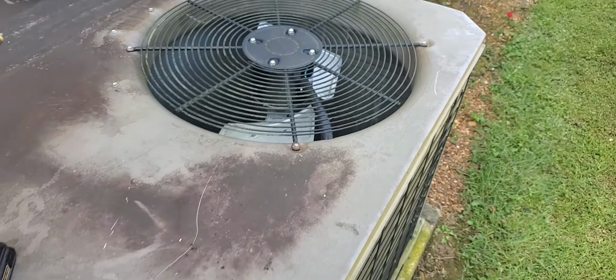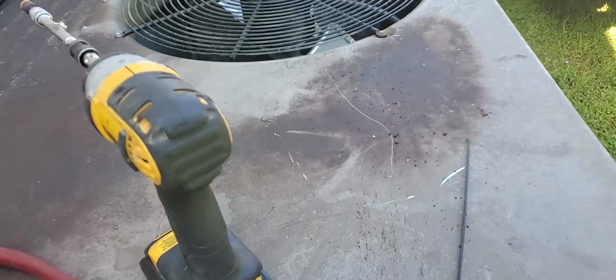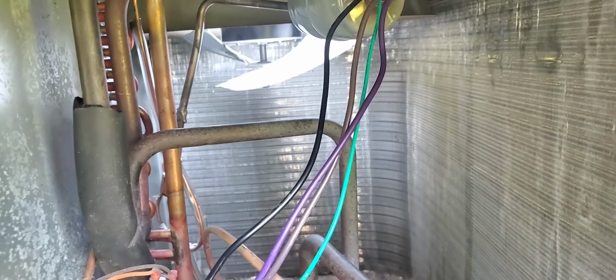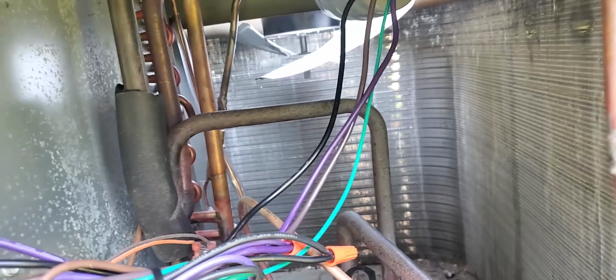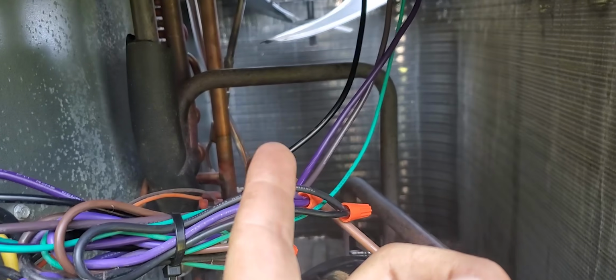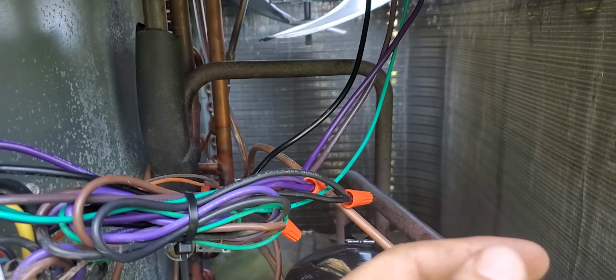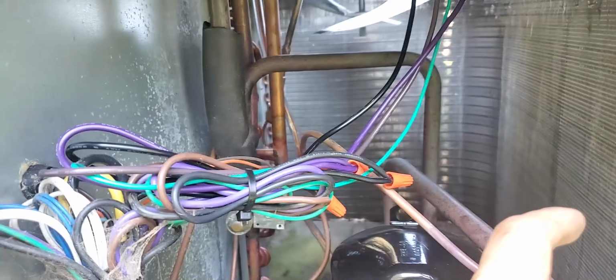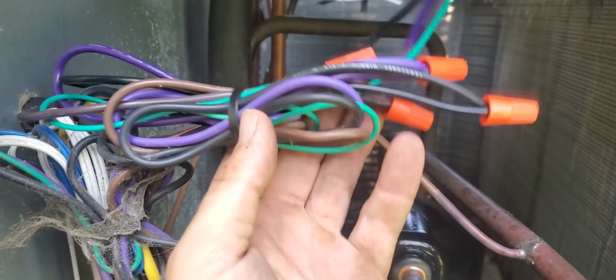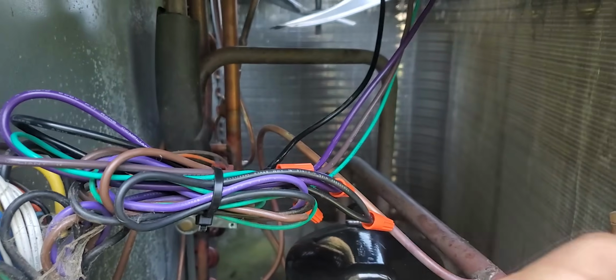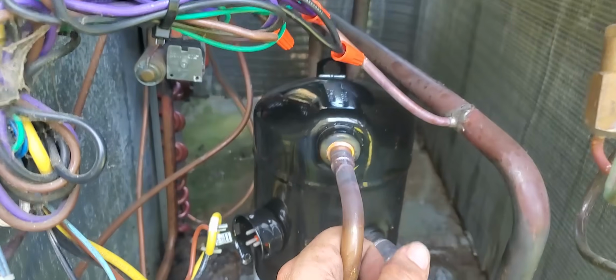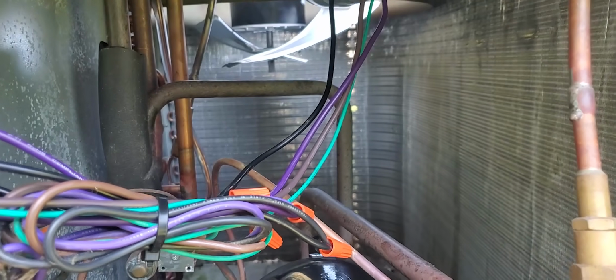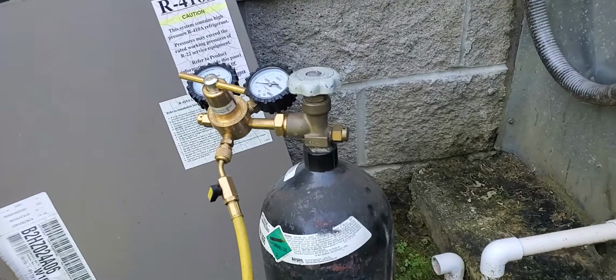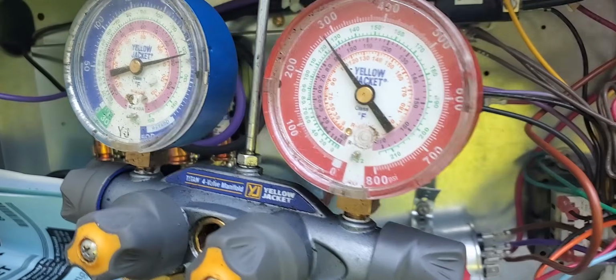I've got the fan blade in the right position on the shaft. That way it's rejecting heat out of the top, and you'll have to check the amp draw when you start the unit up. That way you make sure it's not pulling too many amps, because it could be in the wrong position if it is pulling too many amps. So you'll check run load amps on that motor when you start it up. I've got it wired in. Make sure you have some wire ties with you, and don't leave any of these wires against the discharge line where it could burn through the wires. That's a terrible mistake to make. We're holding the nitrogen nicely on the low and high side.